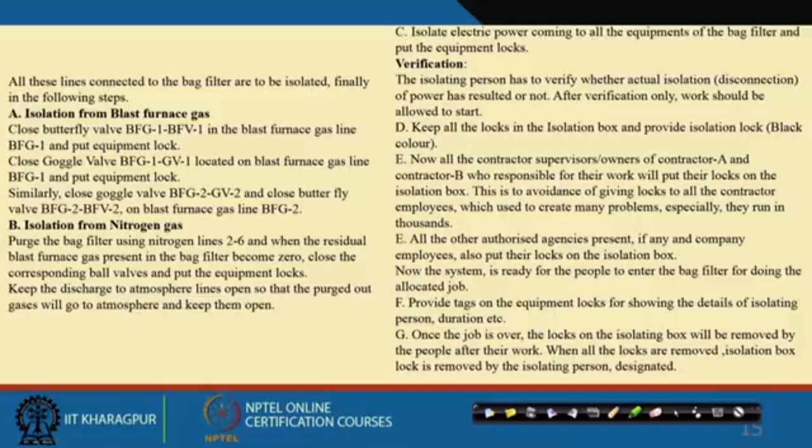Then you have to isolate the electric power, then you have to verify. How do you do verification? By checking inside with the gas meters, whether the gas is coming or not. Then you put all the locks. The people whoever is working, they have to put their locks. They will take out the keys.